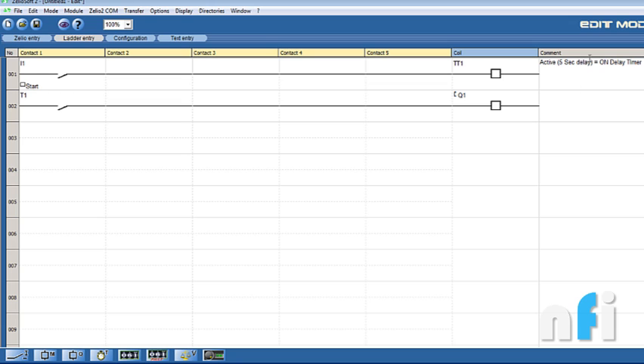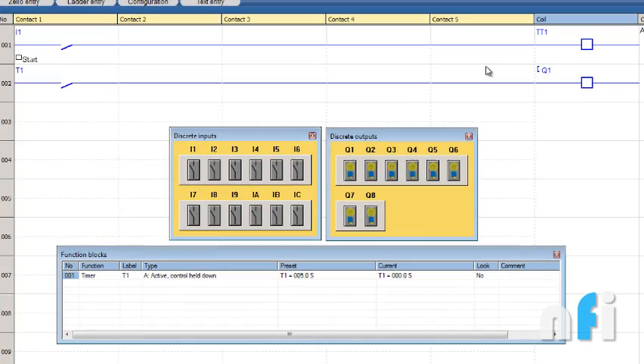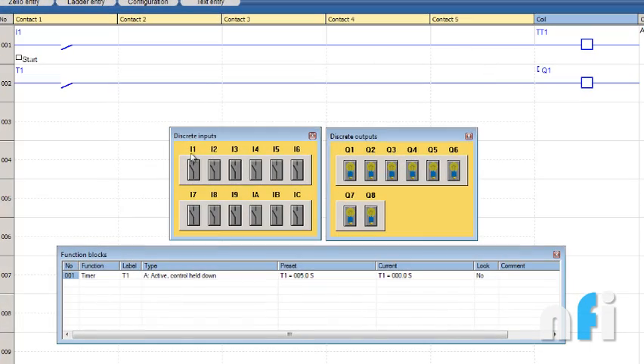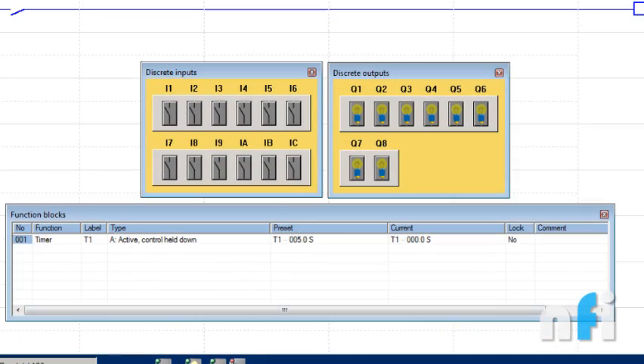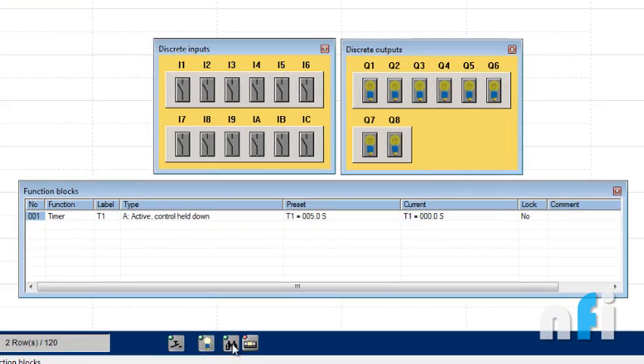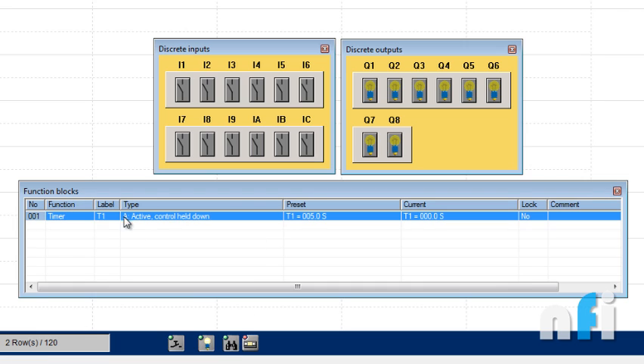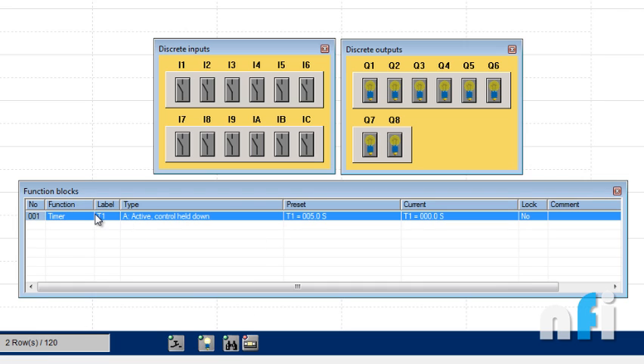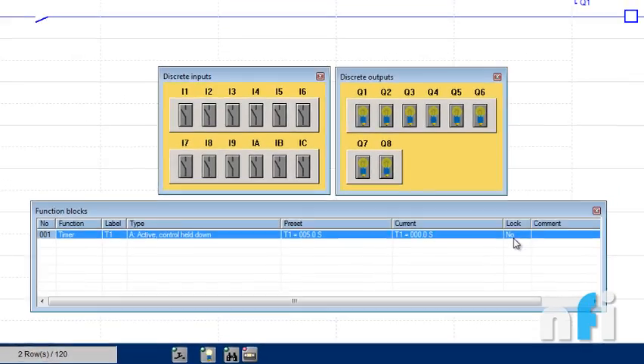Let's go to simulation mode. You have input I1, output Q1. This window for monitoring the timer comes from here, function blocks monitoring. This is timer T1 using Function A, 'Active control held down.' Preset is five seconds, current time or accumulator shows accumulated time, and it's not locked.